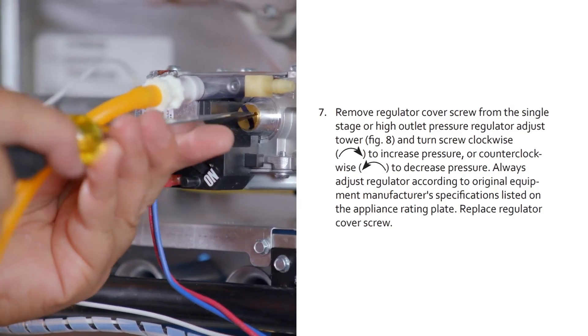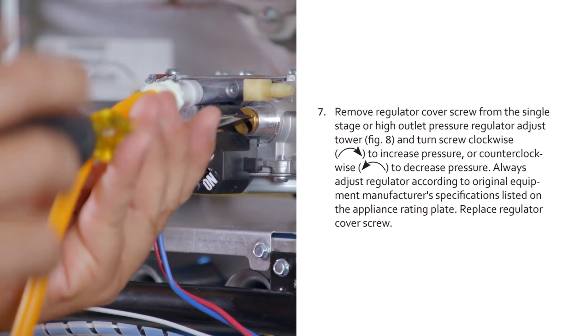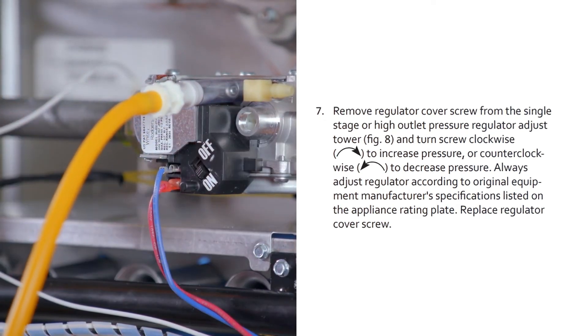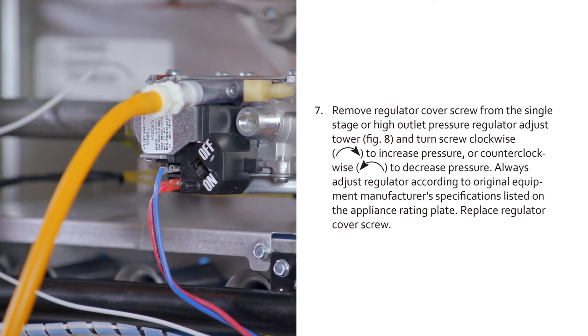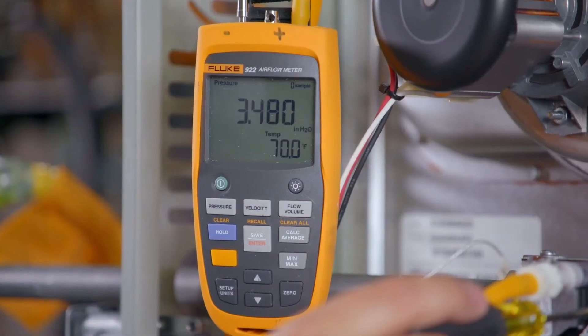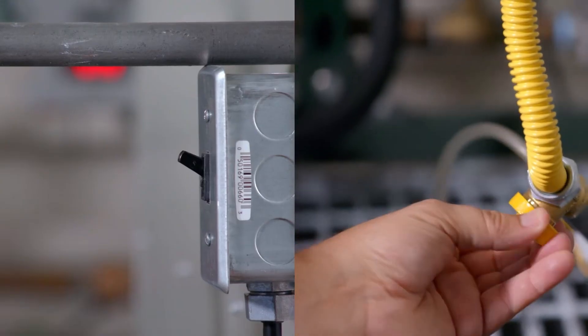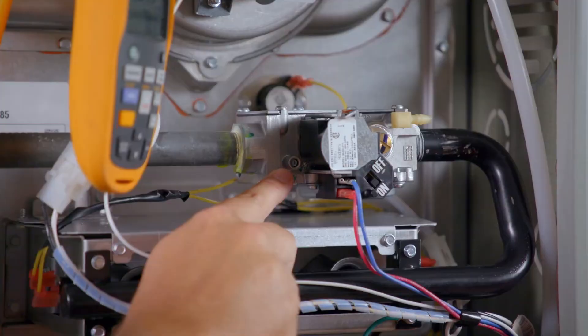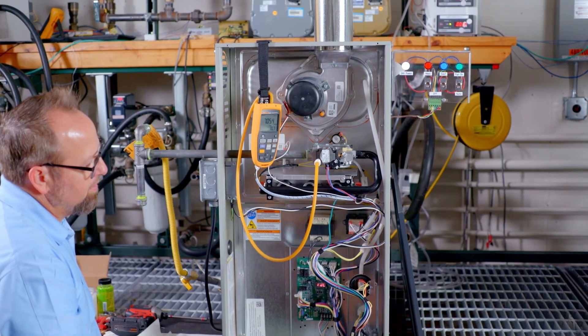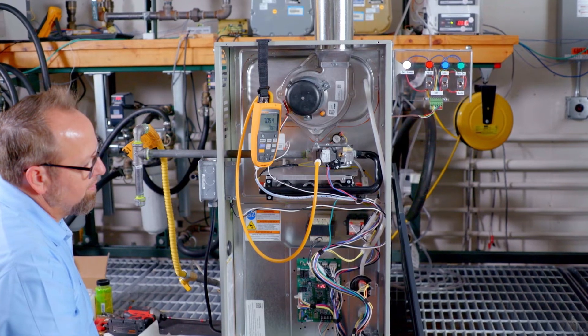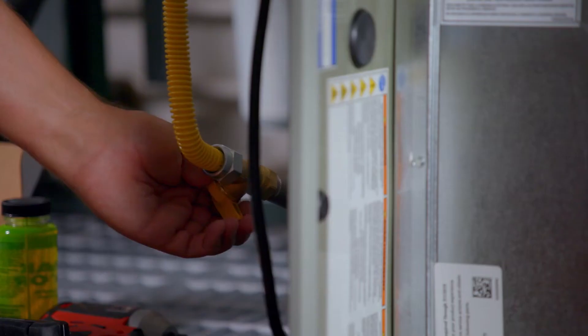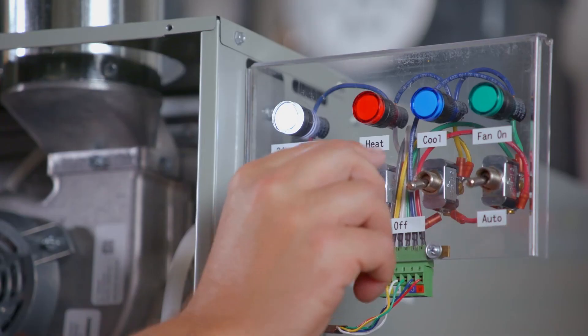If adjustment is necessary, remove the regulator cover screw from the pressure regulator post and adjust. Turn the regulator's plastic adjustment screw clockwise to increase pressure or counterclockwise to decrease pressure. If the outlet pressure cannot be correctly set, the inlet pressure should be checked. Turn off the gas and electric, remove the gas manometer from the outlet post and reinstall it on the inlet pressure post, following the same steps of loosening the pressure tap screw one quarter to one half a turn open. Make sure the outlet pressure tap screw is retightened and secure before turning the gas, electric, and system back on.